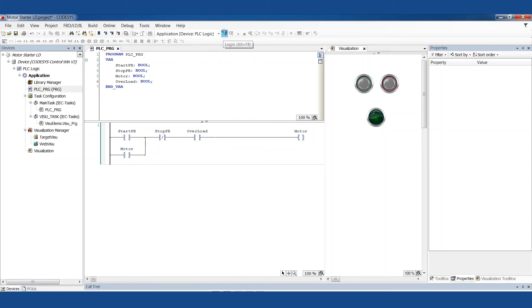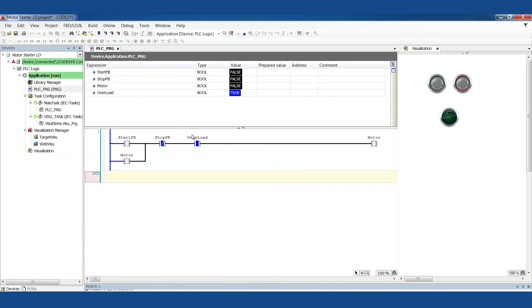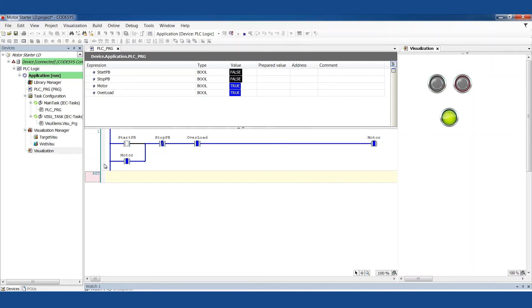Let's simulate this and see what it looks like. The overload is already set as true, indicating it's not overloaded — the system is still able to run. Notice the motor is not on. If I push the start button, all three conditions will be true and the motor will be on. Notice we're latched on. If I push the stop button, this will go false, which will make the motor false and the latch will turn off.